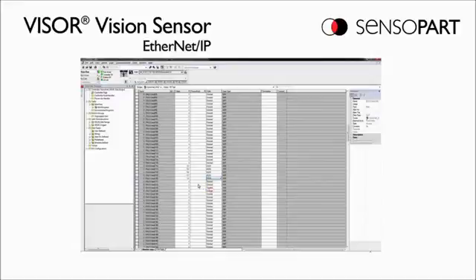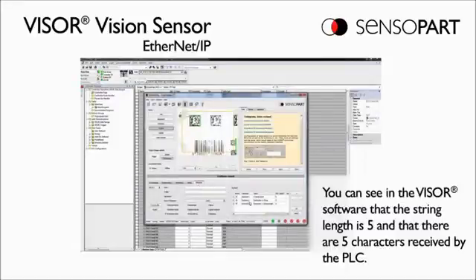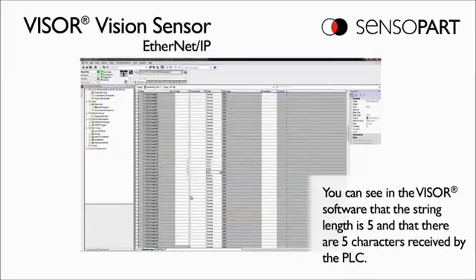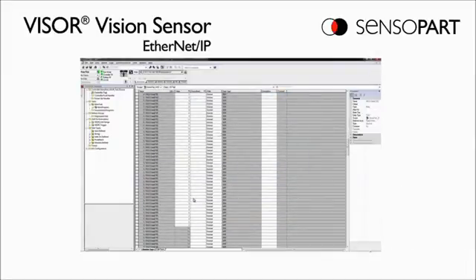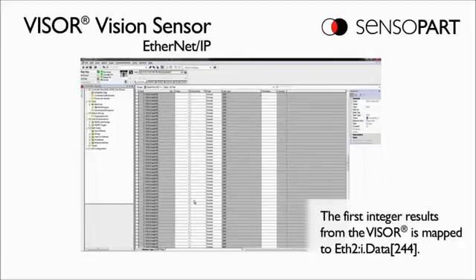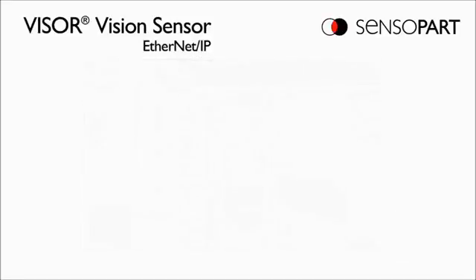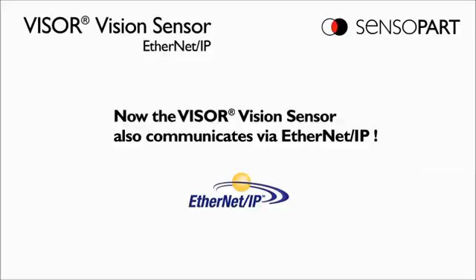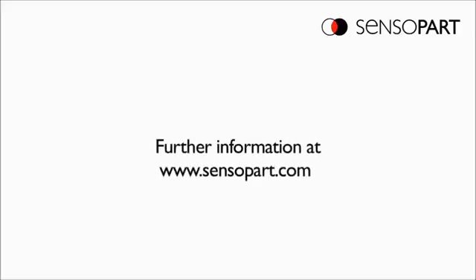Again, it's best to set the length of strings in the detector and in the payload. This will especially help later when converting VISOR payload information into RSLogix tag names. All integers get mapped into this area starting at element 244. This includes integer, single, and double integer tags, and floating point from the VISOR, which are, again, integers with the implied decimal point at 3 places. That's the EtherNet IP introduction. Check back for more videos.